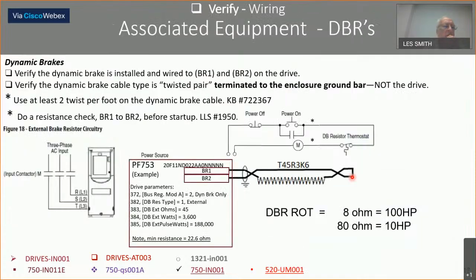We're under associated equipment here. And again, off of the AT003, verify the dynamic brake is installed to BR1 and BR2. It may not always be BR1, BR2, it might be BR plus, BR minus, but there will be two connections on a drive, if it has a chopper, to attach that resistor to it. I check that to make sure that it is. Verify the dynamic brake cable is twisted pair. If you have dynamic brake cables, they should be twisted.